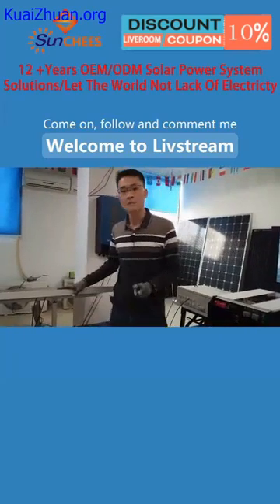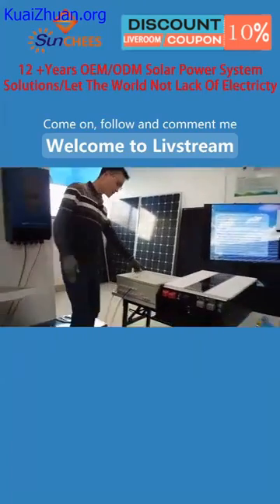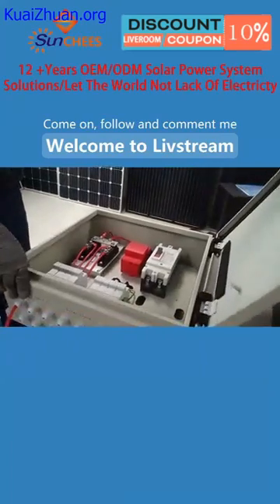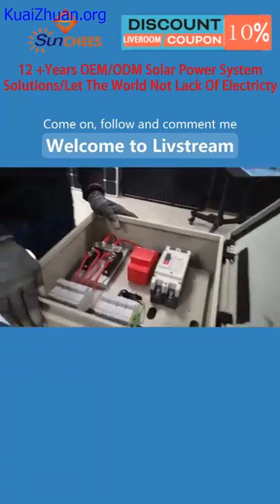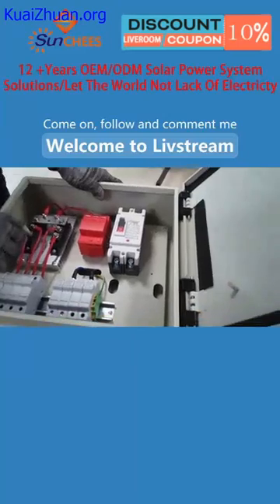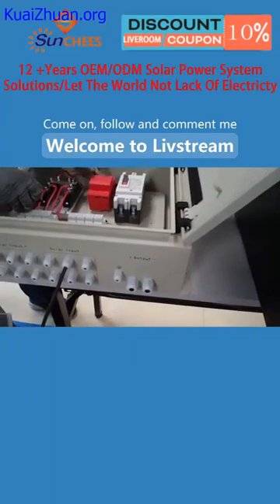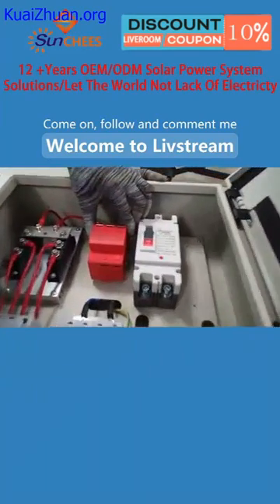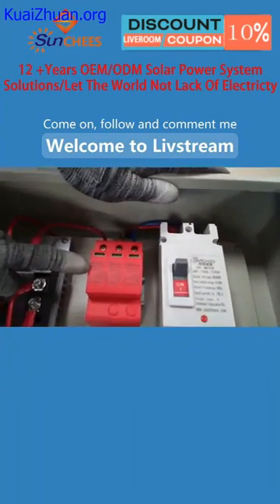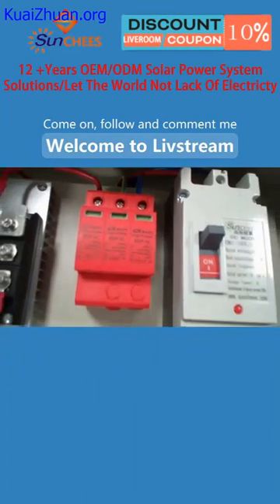And the second part of the solar power system will be the PV combiner. This is our PV combiner. The PV combiner's function is to simplify the wiring between the PV array and the hybrid inverter, and supply protection against lightning, high current surge, and other hazards. And you can see the red one is the surge arrestor. It can supply the protection function for the complete set solar power system.